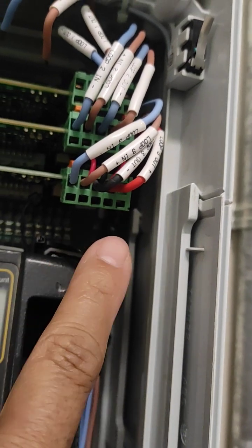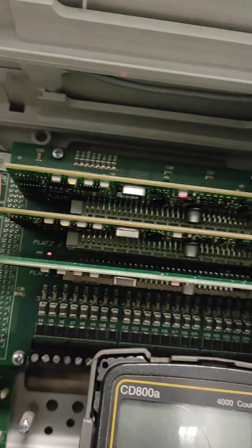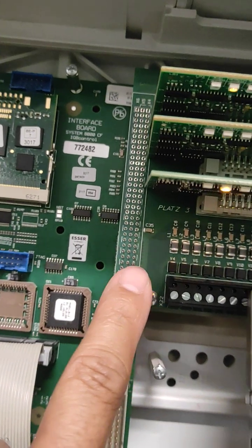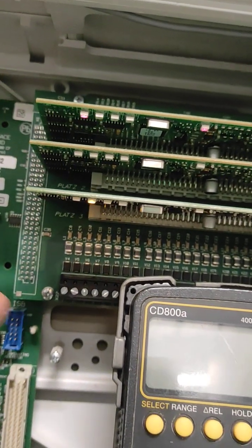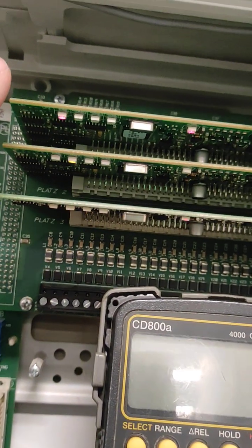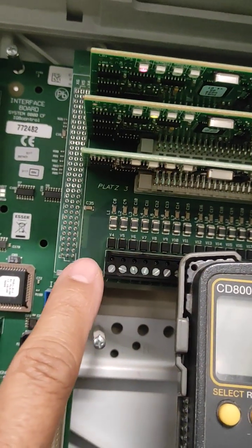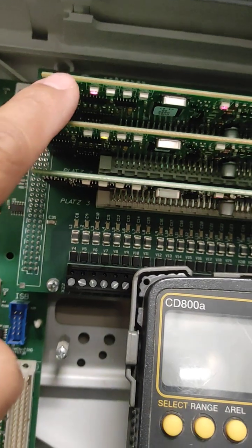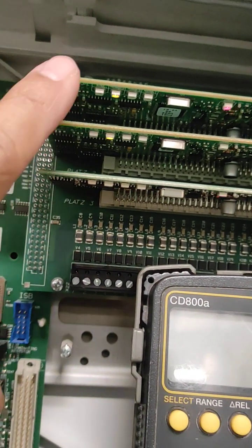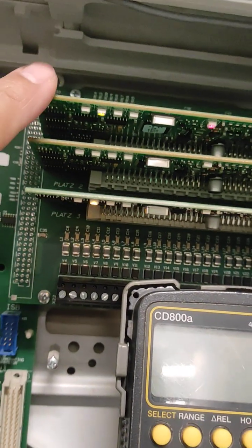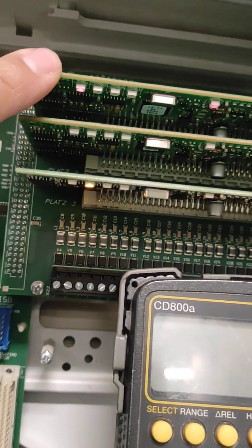This is the IQ8 control M, and this is an extension module, also called a micro module, and this is the loop card. For each micro module we have 3 SLC loops, or signaling line circuit loops, and for each loop card we have 127 devices.